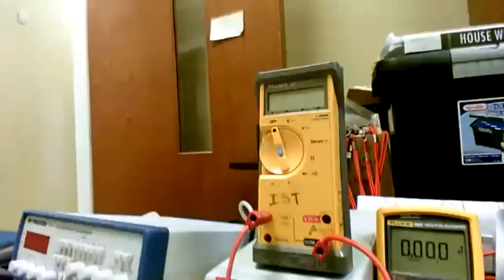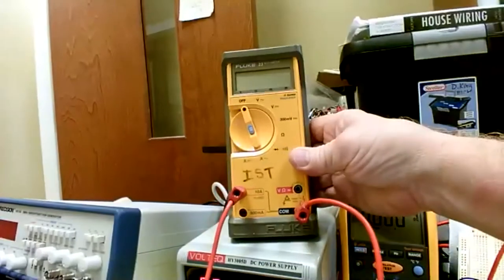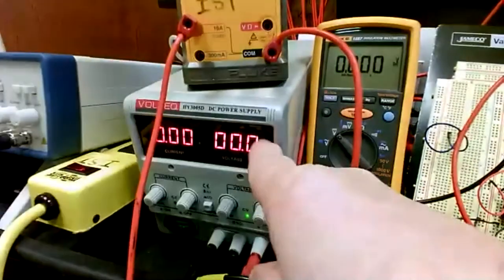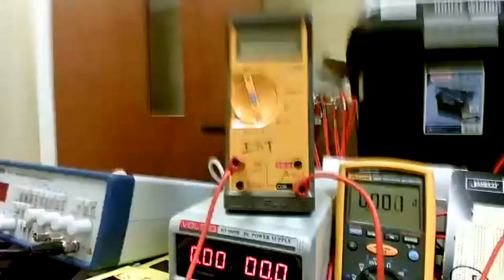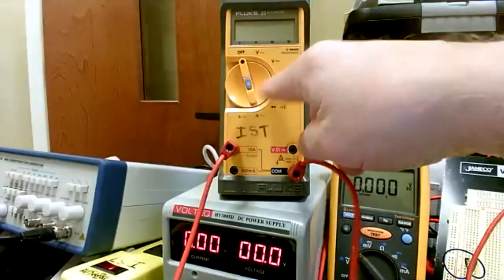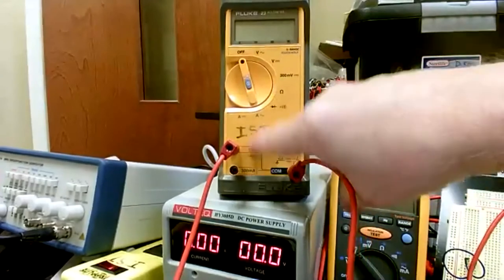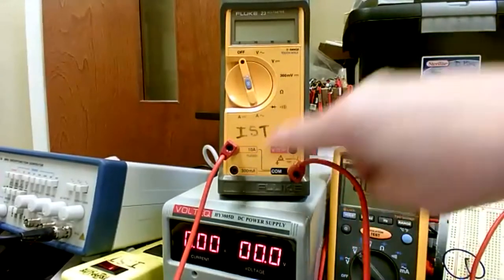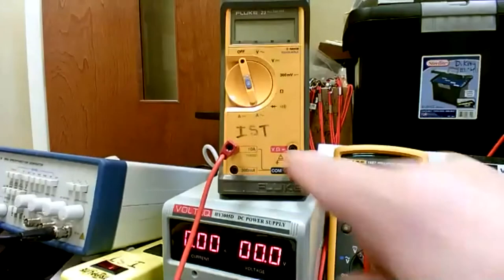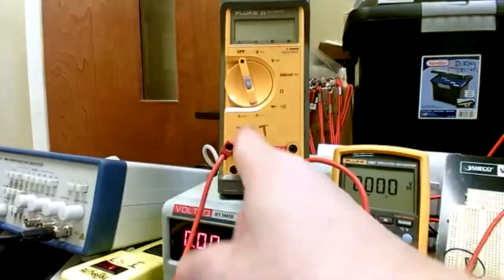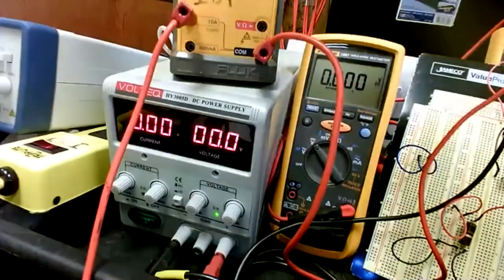what can happen is if you have power on here and then you cut the meter on or change some position, I've seen it actually pop a fuse in there when you get a surge through the meter. So you're better off on the ammeter connection to power it down before, and then cut the meter on.